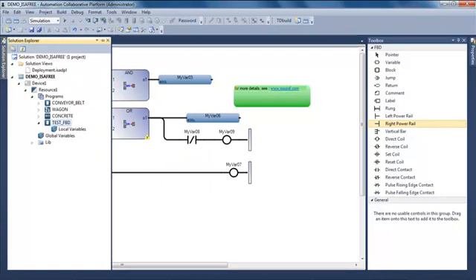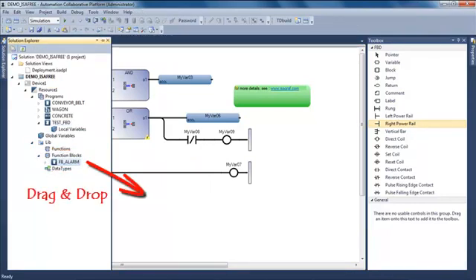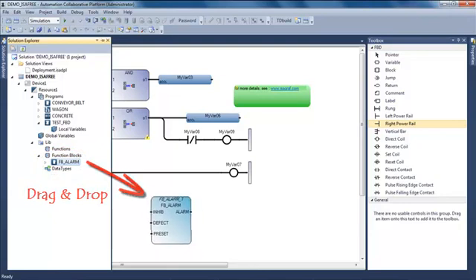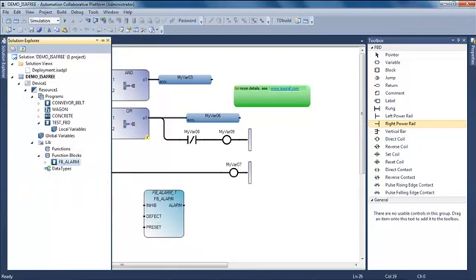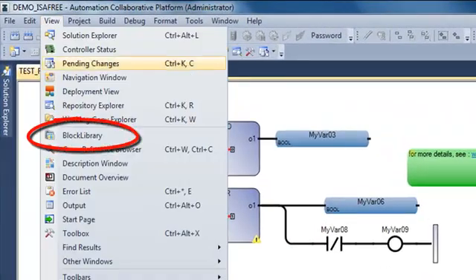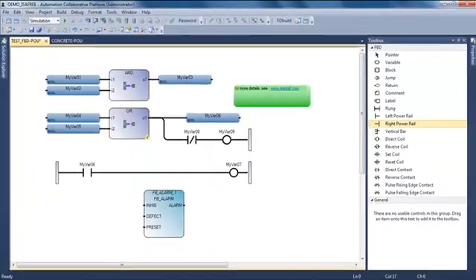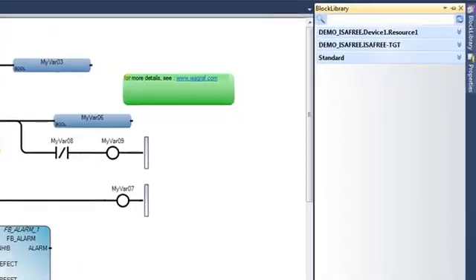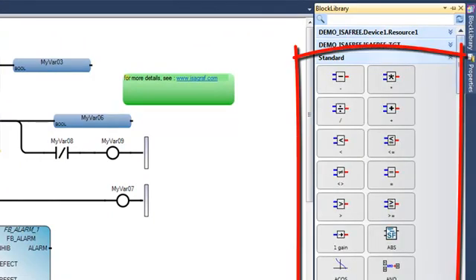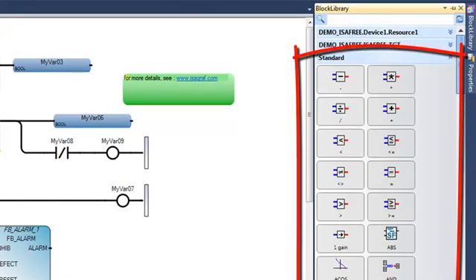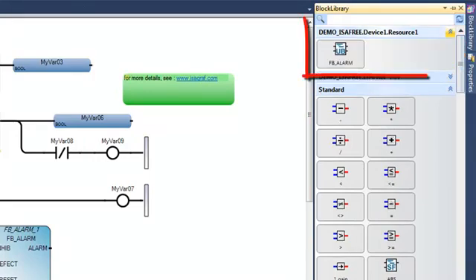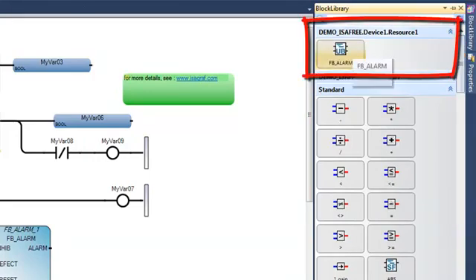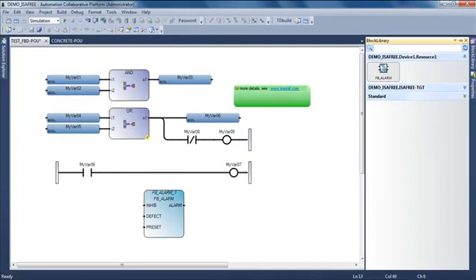When I want to insert a function or a function block, I can also drag and drop this function and function block from my local library. I can also open the block library where I'm going to find all the operators defined by the 61131 standard or all the functions and function blocks defined in my local library.